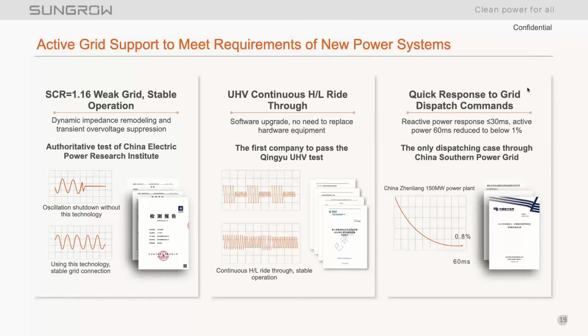One of the big highlights that I want to showcase here, and one of the big takeaways, is the improved reactive power response time. It's going to be around 30 milliseconds from dispatch to receipt. So that's extremely fast for reactive power response time. And then active power ramp rates are going to be somewhere around 60 milliseconds. Our ramp rate and response time on the active power with all of our inverters has always been incredibly fast, and the margin of error of that has been reduced to somewhere below 1%. And all of these tests have been verified by the most rigorous labs in China. And we also have TUV Rhineland and TUV SUD, as well as DNV and UL verifying these results as well.